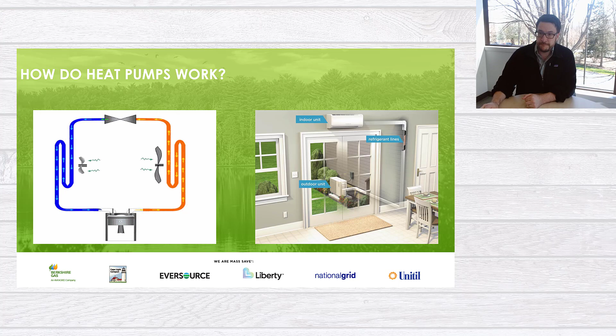So we haven't yet talked about why a heat pump is so much more efficient than other types of heating systems. So let's do that now. Say if you were to buy 1 gallon of fuel or 1 therm of fuel, and you were to put that 1 unit in a heating system, depending on the efficiency of the heating system, you're not going to get out the full unit in heat to the home. So a lot of that energy in an older heating system may be going up and out the chimney. Other heating systems may have a lot of jacket losses, and that energy is just being lost to the slab in the basement.